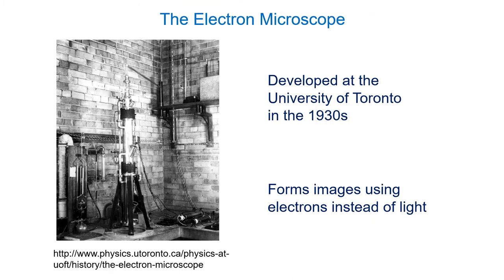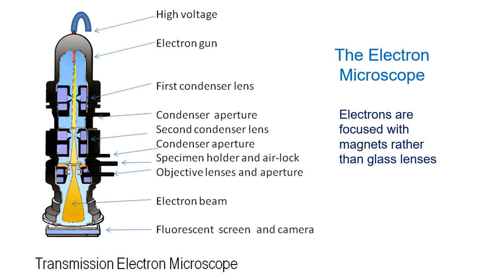One of the major players in the early development of the electron microscope was the University of Toronto. In an electron microscope, electrons are forced into a tungsten wire at the top, liberating electrons that flow down to a specimen. The fundamental structure hasn't changed much: at the top is an electron gun containing a tungsten filament similar to an incandescent light bulb. A high voltage passes through it, liberating high-energy electrons that form an electron beam. Since electrons have mass and can't pass through glass, we use electromagnets rather than glass lenses to focus the beam.